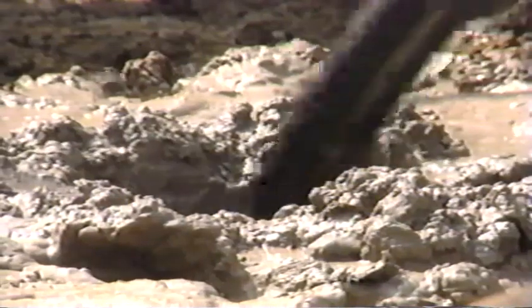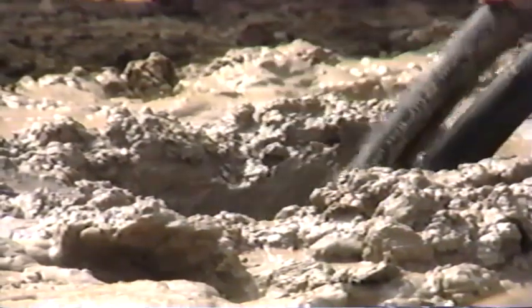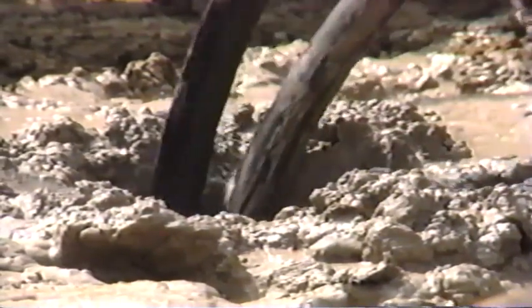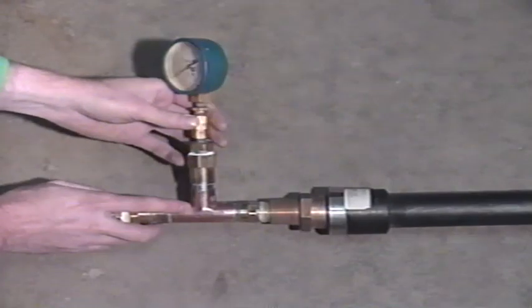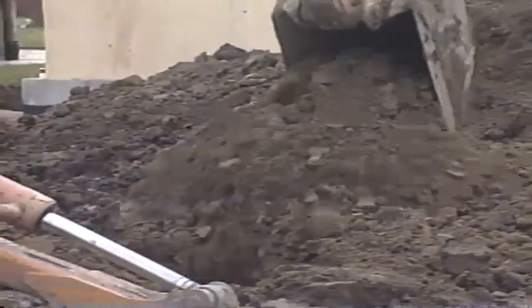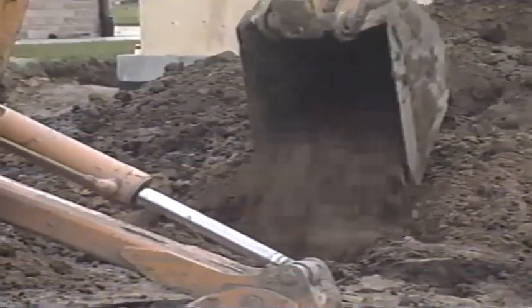On large properties, earth loops can be installed horizontally 4 to 6 feet deep with a backhoe or chain trencher. On smaller lots, drilling equipment is used to bore small diameter holes 50 to 200 feet deep. 2 pipes, joined with a U-bend, are then inserted vertically into each hole. The pipes are then pressure tested and backfilled. Depth is of secondary importance, since one deep loop performs the same as several shallow ones.